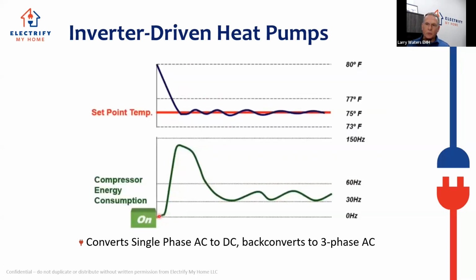So instead of starting up with a lot of energy, this unit starts from a single rotation and slowly ramps up. And once it establishes the revolution and the movement of the refrigerant through the system and the pressure difference is low, then it ramps itself up. It starts speeding up and it takes care of this temperature change in the room pretty quickly. But instead of overshooting or passing the set point temperature, it gets down to set point and it slows down. And so what we see here in these little hills here is the cool air going into the house and the furniture and everything in the house releasing its heat to the cooler air, and the thermostat responding with small changes in the capacity just to overcome those little balances in temperature as everything in the house is getting to temperature. And so we call this the tempering phase.